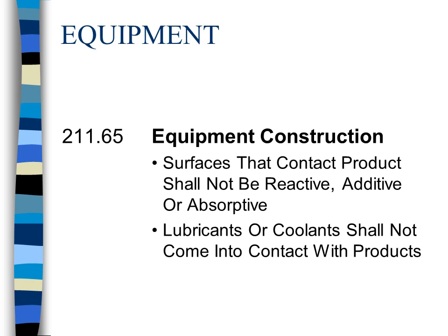Lubricants, by their very nature, are petroleum-based products. Very, very few lubricants are oxygen compatible. Coolants are petroleum-based products. So there is your fuel, your first item, a lubricant, petroleum product.